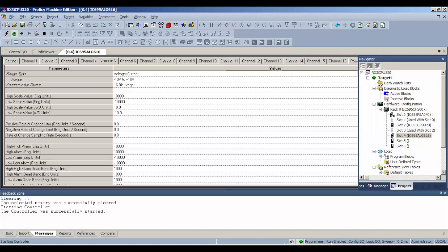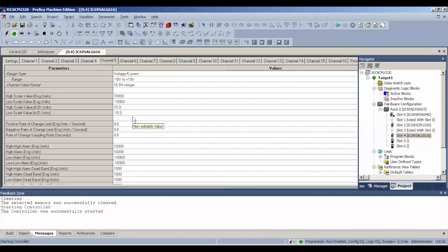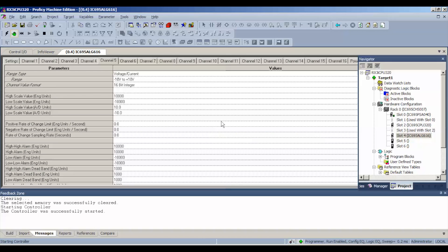If for some reason it doesn't, or if you're still stopped or if it's faulted, go to your feedback zone and find out why. This is my feedback zone located here and it'll give you information. If it's not in run mode, you could also simply open up the processor's battery door, the reserve battery door, and make sure that your input-output lever is in the far right position. It's a switch that goes from left to right. It should be in the far right position to enable the outputs.